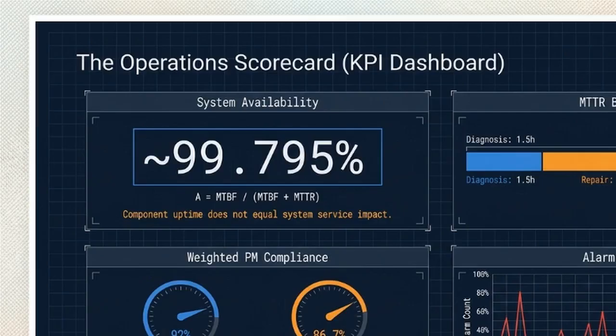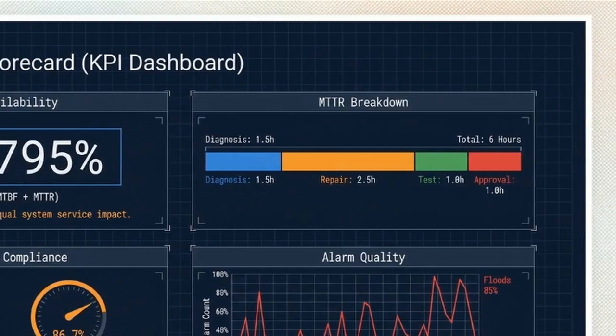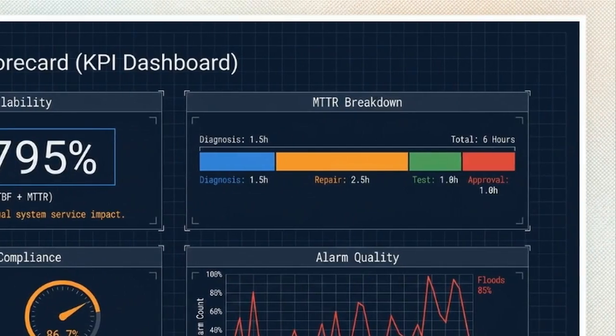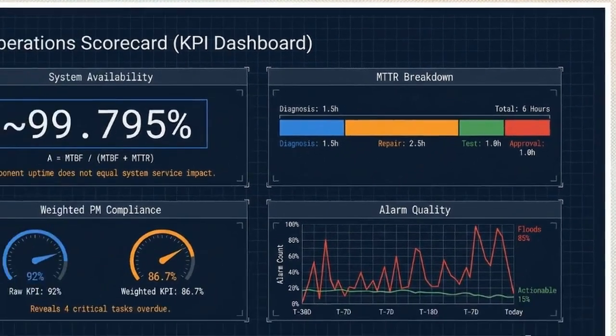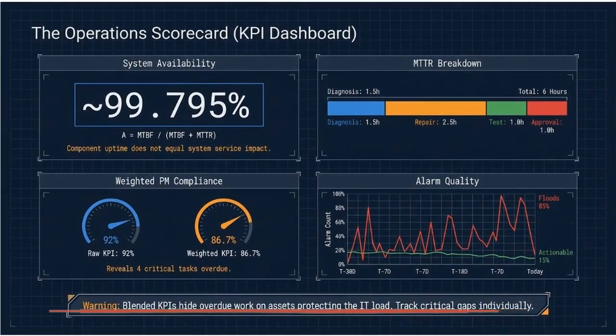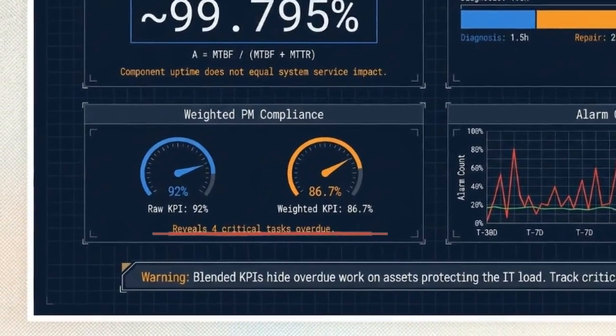This operations scorecard dashboard illustrates a key distinction. Component uptime does not equal system service impact. A chiller can have a high mean time between failures, but if its downtime aligns with a peak load event, the service is compromised. Notice the warning banner at the bottom. Relying on blended KPIs can mask overdue work on specific, highly critical assets. Gaps in protective equipment must be tracked individually to maintain true redundancy.